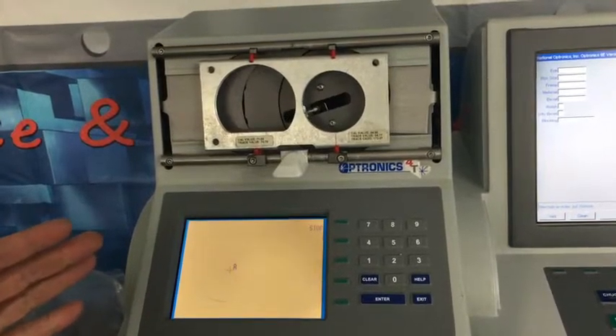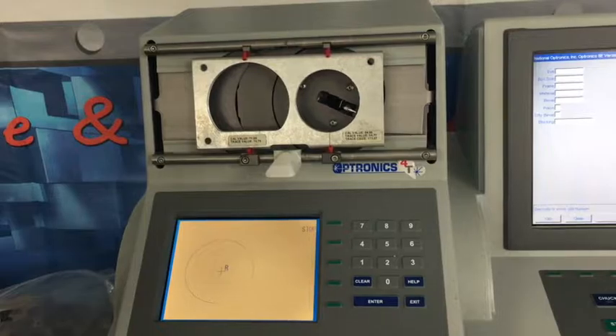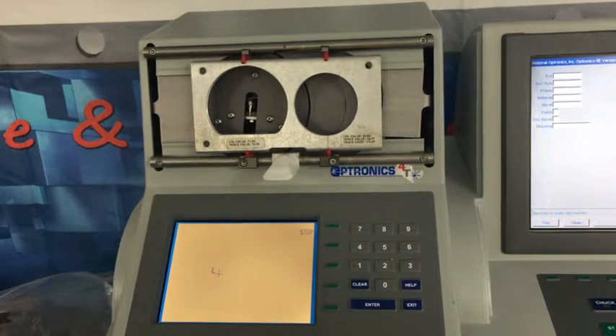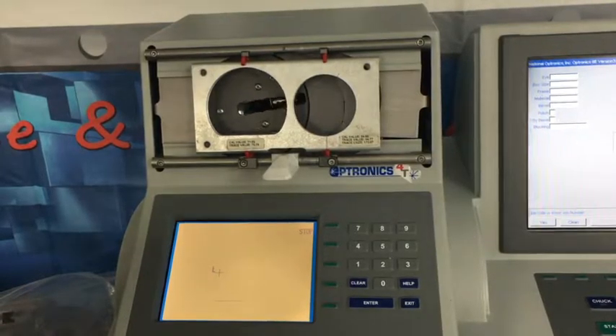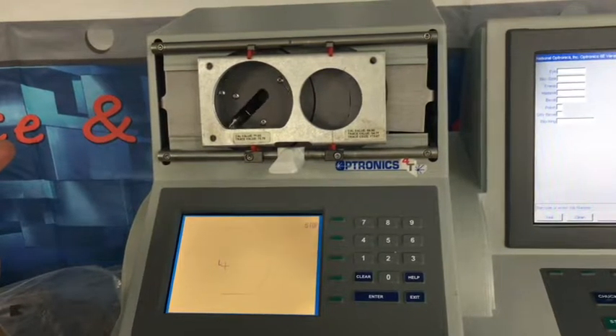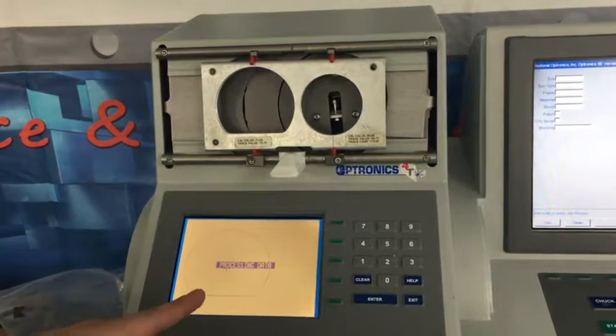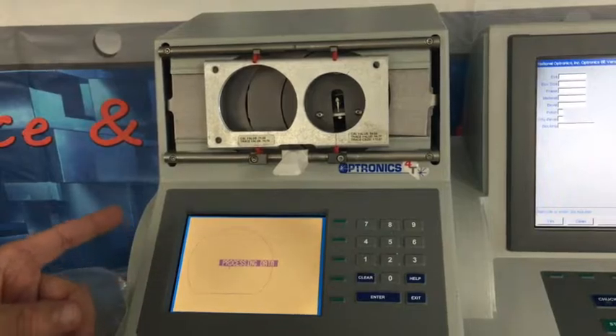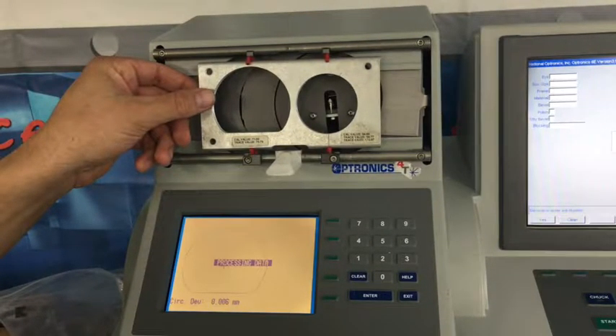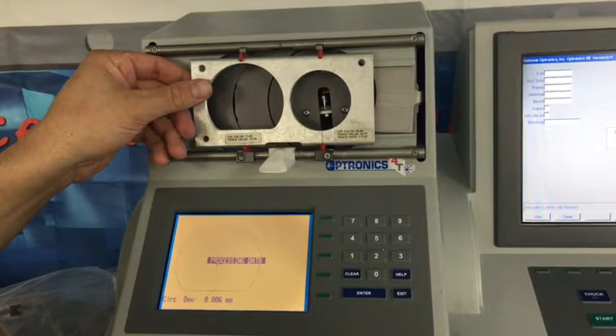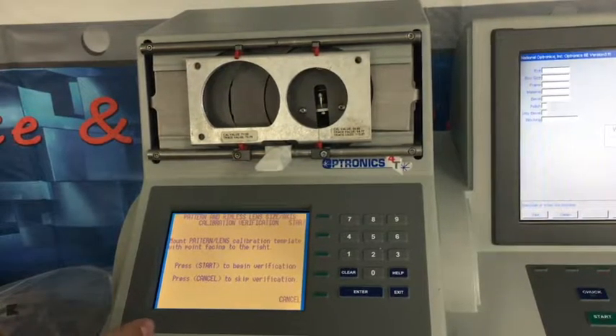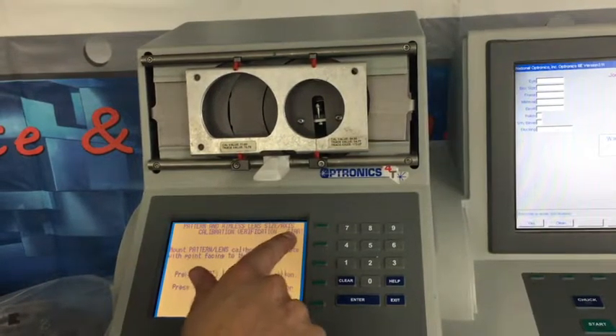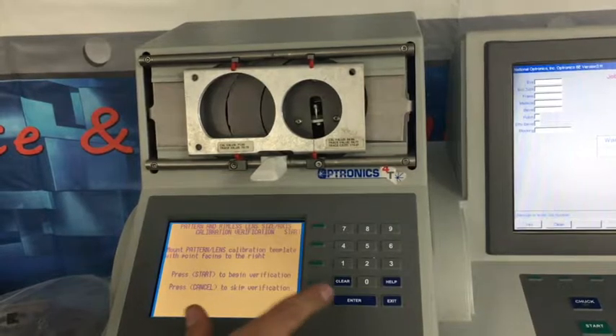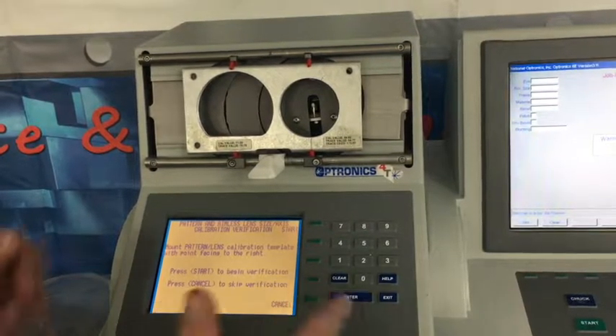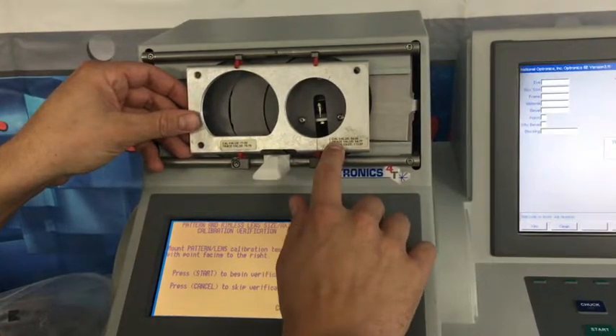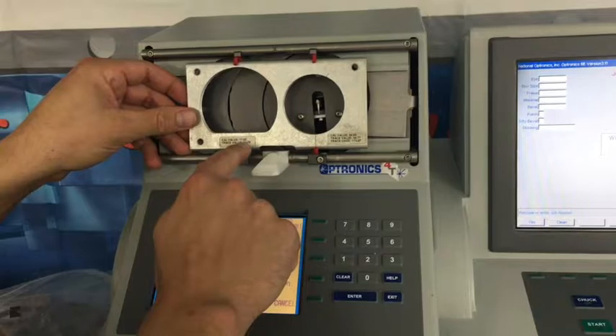What this one is doing is it's calibrating a frame size, so this way it gets an accurate measurement of your frame and bevel position. And that should take just a few more seconds. Processing data takes another few seconds, and it should say completed. And there we go. If it didn't calibrate correctly, it'll say up here calibration failure, and it'll ask you to do it again. So all you have to do is just hit start again, and it'll run the same process until it calibrates correctly. Because what it's doing is it's trying to calibrate itself to these values right up here.